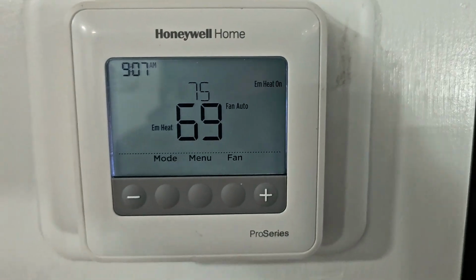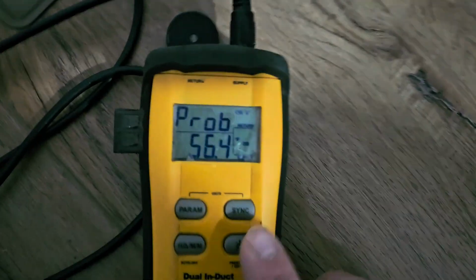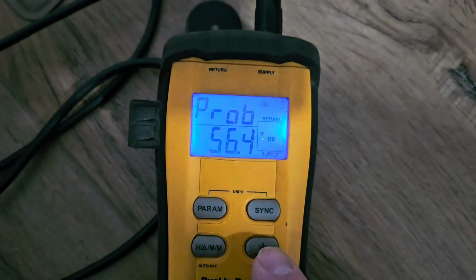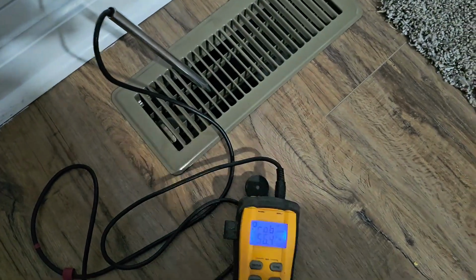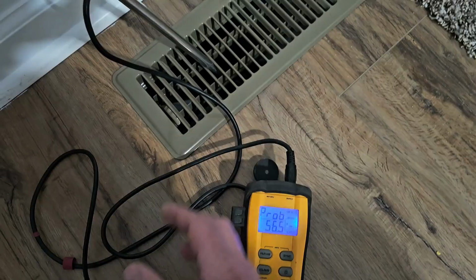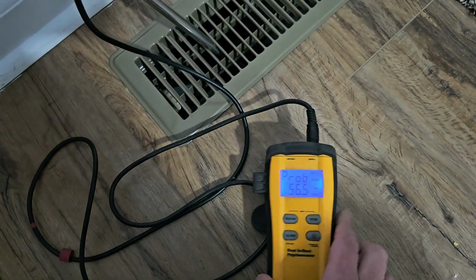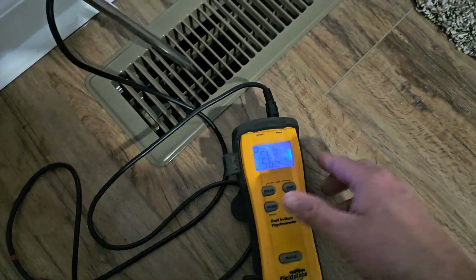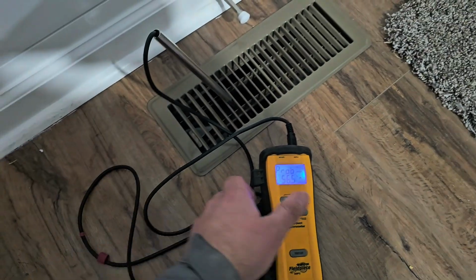All right, let's go check the temperature coming out of the vent. All right, it is 56 degrees coming out of the supply vent. It's definitely not working. We've given it enough time to engage. You wait, you know, a couple minutes, wait 5 minutes to make sure the heater kit has time to engage, but it's not working. Now, I'm going to show you another tool you can use to check it.